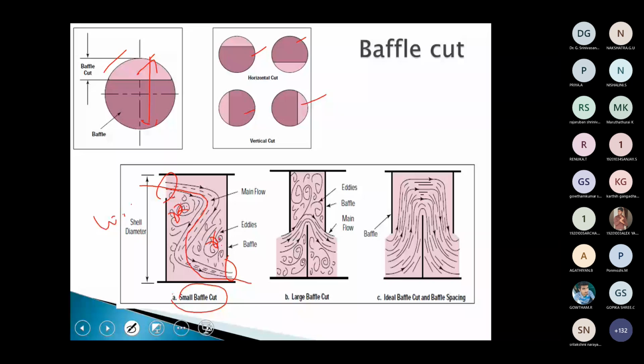Similarly, if the baffle cut is very large, you can see the flow may be like this. So here also eddies and dead zones occur, and again the heat transfer rate goes down. In order to have a very good heat transfer rate, you should have an optimum baffle cut. With the optimum baffle cut, the flow should be like this. This is what we call the ideal baffle cut. Also the baffle spacing should be ideal. It should not be very close or very large.